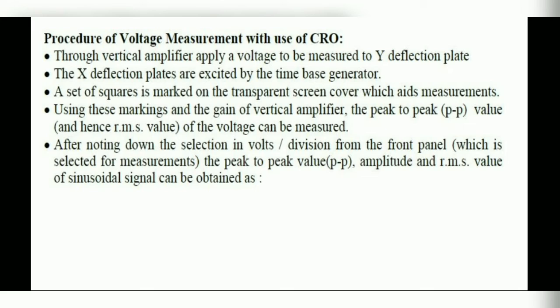Next is the procedure of voltage measurement with the use of CRO. Through the vertical amplifier, apply the voltage to be measured to the Y deflection plates. The X deflection plates are excited by the time-base generator. A set of squares is marked on the transparent screen cover which aids measurements.